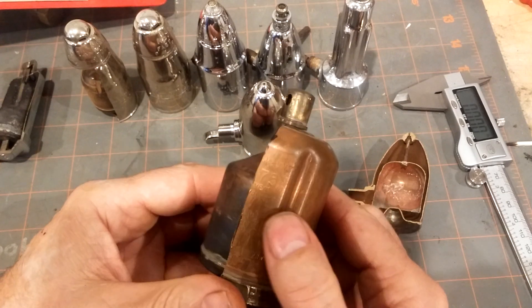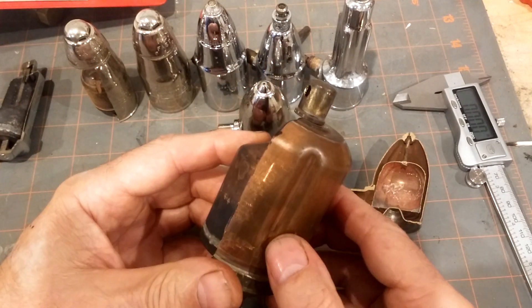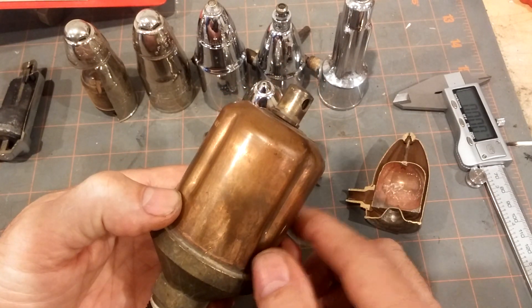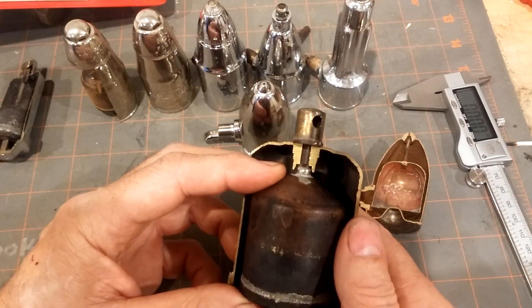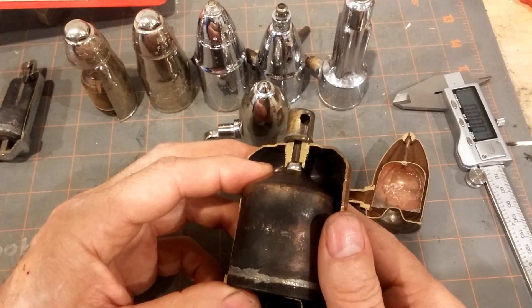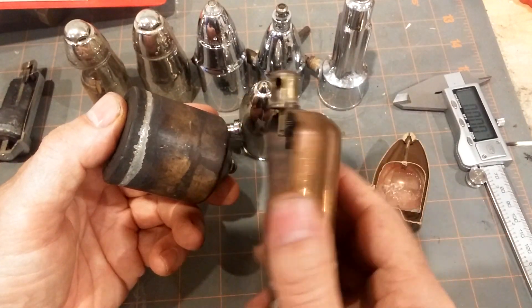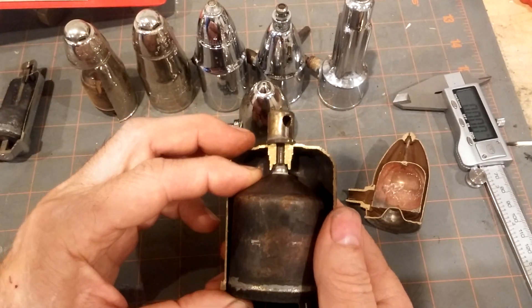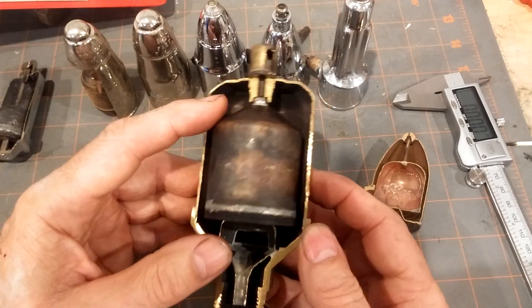I have noticed, however, that the Hoffman 75s fail at a little higher rate than they should. Back when they were painting these things green they seemed to last longer. When they stopped painting them green, I think they also probably dropped their quality control standards a little bit, and these things seem to be failing at a much higher rate than the older ones. The old adage — they don't make them like they used to — might actually be true in this particular case.